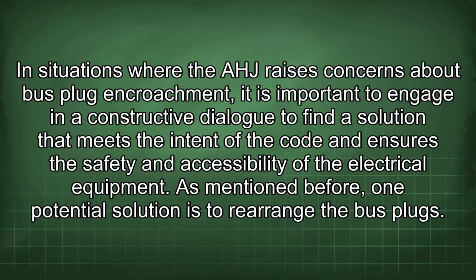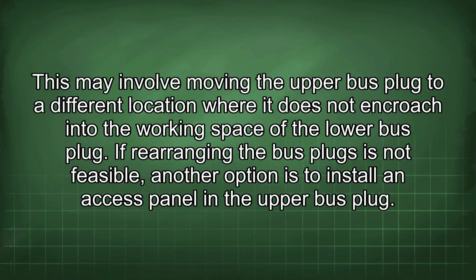In situations where the AHJ raises concerns about bus plug encroachment, it is important to engage in a constructive dialogue to find a solution that meets the intent of the code and ensures the safety and accessibility of the electrical equipment. As mentioned before, one potential solution is to rearrange the bus plugs. This may involve moving the upper bus plug to a different location where it does not encroach into the working space of the lower bus plug.